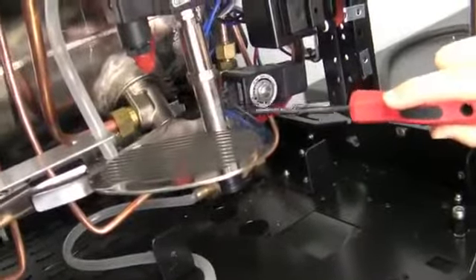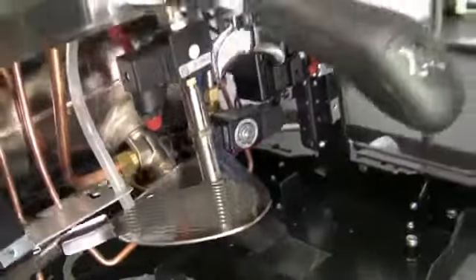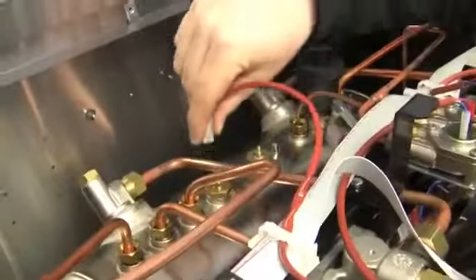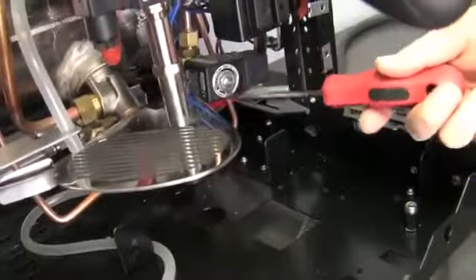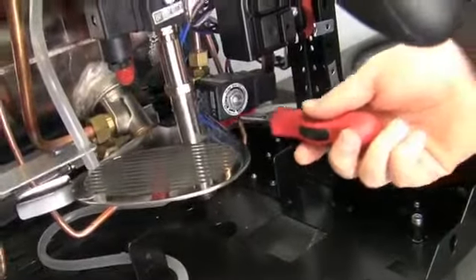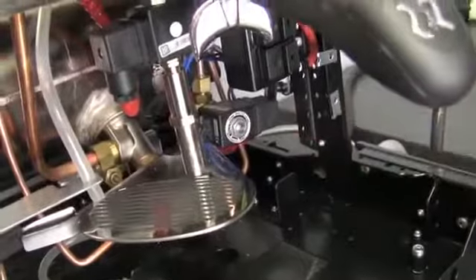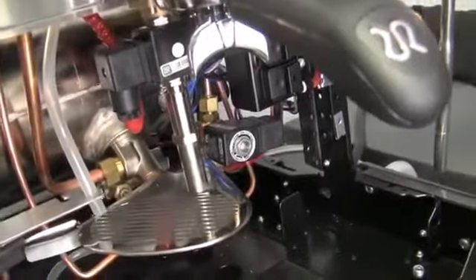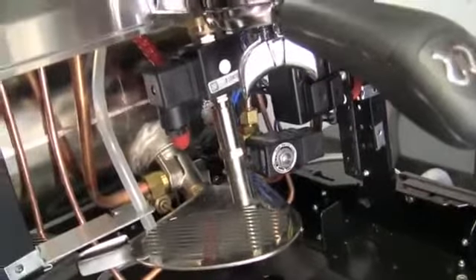This is what gets turned on when we were up here with this little water level probe. When this thing goes off and says I have no water or I'm low on water, it sends a signal to this little black box, which is called the inlet solenoid. The box itself is actually called a coil, it's a magnet. It's going to open up and let water in, and you're not going to be able to see this, but it just basically goes up and into the boiler. That's all that does.